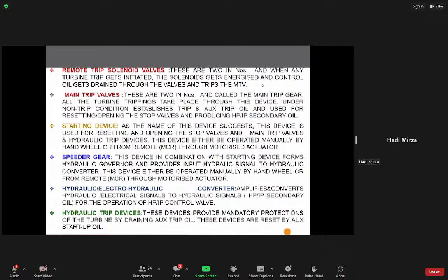This is a mechanical device. In this, there are two pilots, an auxiliary pilot and a main pilot. Basically, in this main trip valve, control oil converts into trip oil and auxiliary trip oil. That is what is written here. And then trip oil will convert into secondary oil, HP secondary and IP secondary.